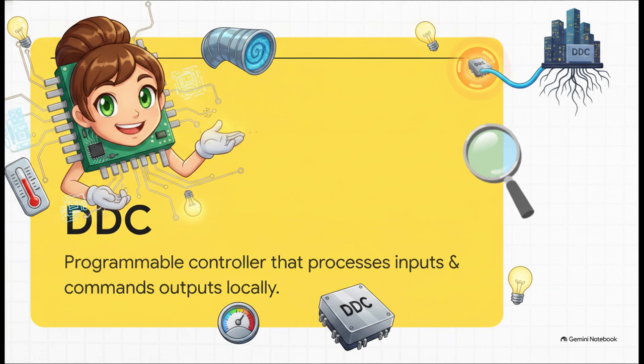And here is why DDCs are total lifesavers. They operate completely independently. Seriously, if a main network cable gets sliced by a contractor or the central server crashes, these local brain cells just keep chugging along. They make sure the HVAC keeps running safely so the building doesn't literally suffocate just because a computer went offline.